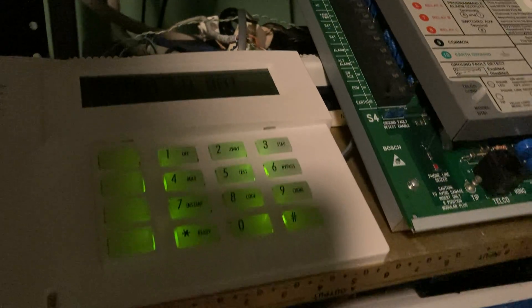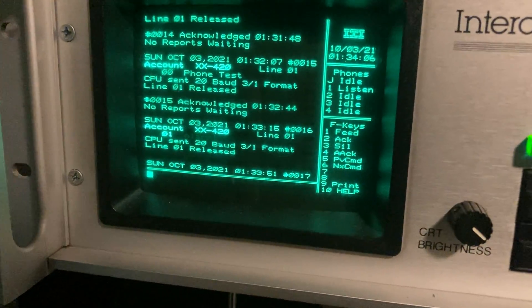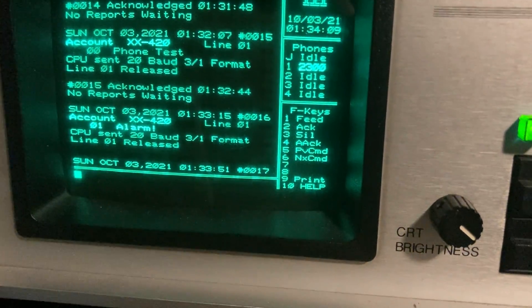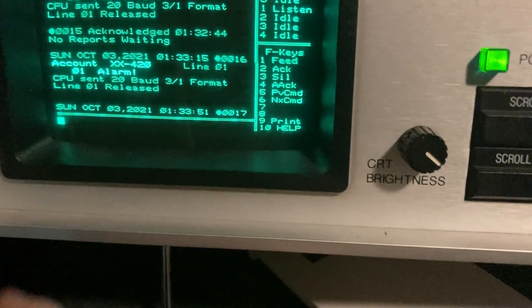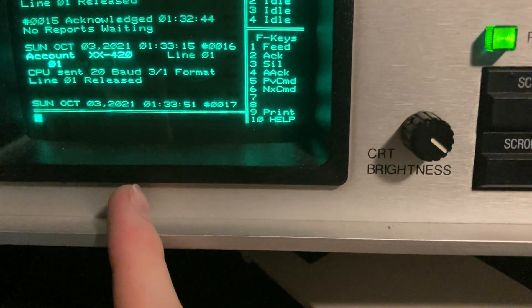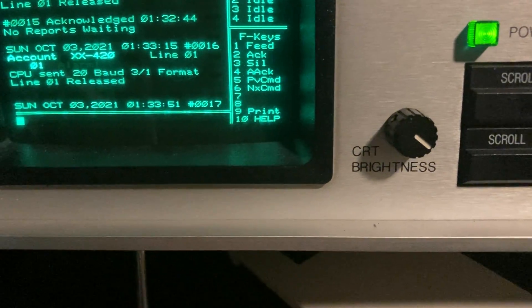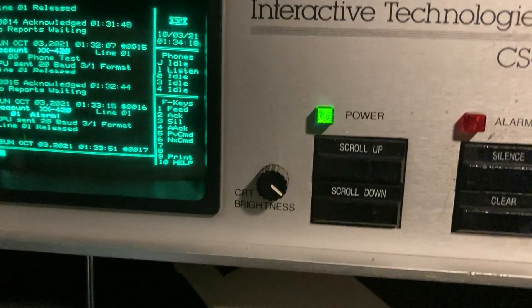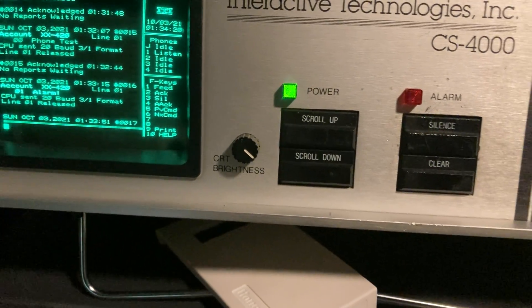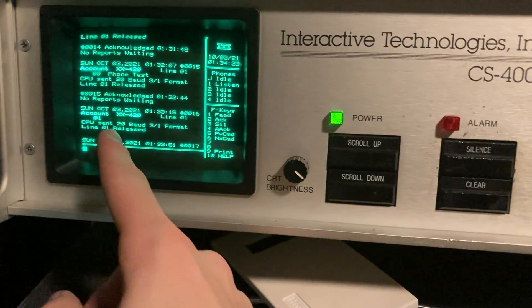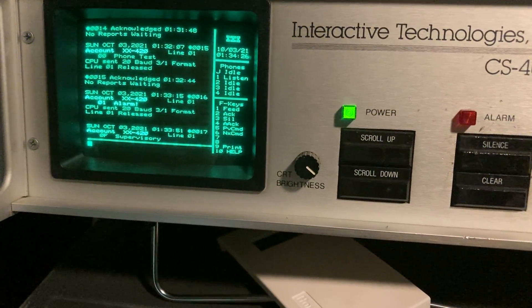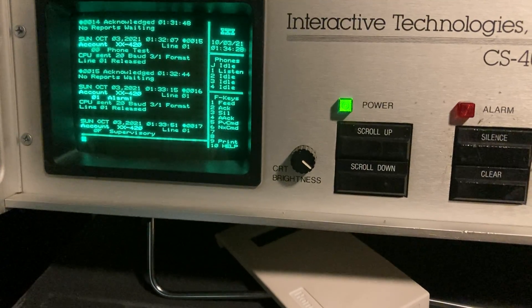There we go. That was a weird thing, did you hear that? It's entering the code and it just faded out. Yeah this Vista's for you. Anyway, receiver operated just how it should. So gotta like that flashing alarm text there and it highlights it. So there we are and CPU sent standard format and now we're sending the cancel report. So it activated the buzzer in the receiver for that alarm because it wasn't canceled in the same session, and we got a supervisory for the battery trouble it came in.